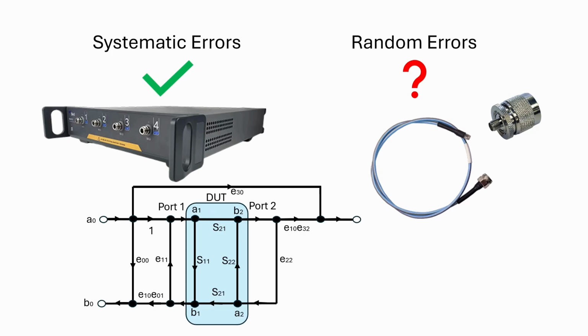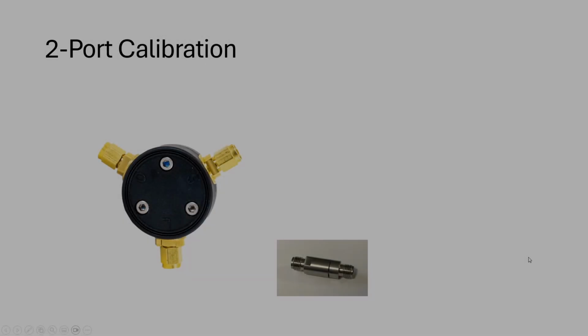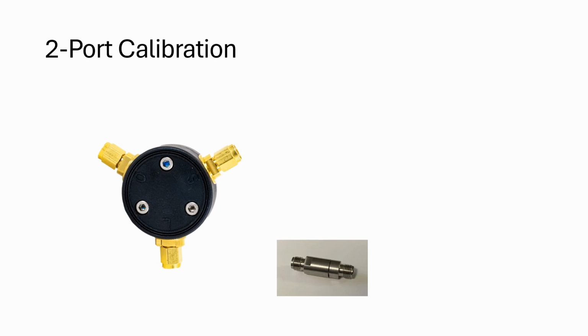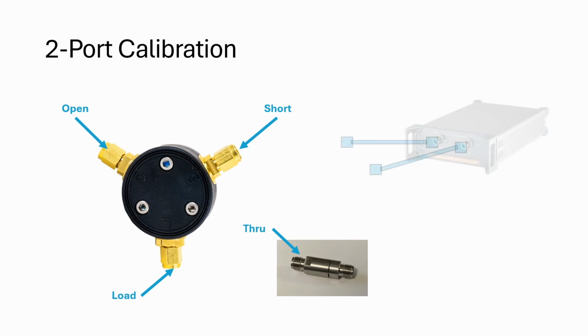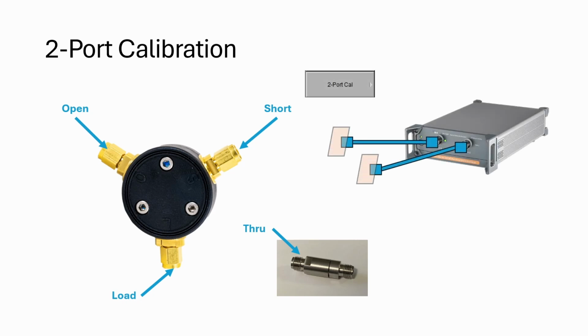Random errors in the form of contributions from things like cables and connectors will also be minimized but not fully removed. The full two-port calibration requires an open, short, and load standard connected at the calibration plane for each of the selected ports of interest where measurements are to be made. Additionally, a through standard is used to couple the ports together.